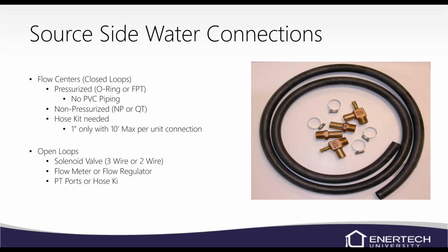On an open loop, we don't normally use a hose kit. We'll use a solenoid valve, either a solenoid valve with an end switch, which is a 3-wire valve, or a solenoid valve without an end switch, which is a 2-wire. We'll get into a little bit of the open loop wiring for the solenoid valves towards the end of the training today. With an open loop, you'd have to have a flow regulator or some type of flow meter to control that flow.